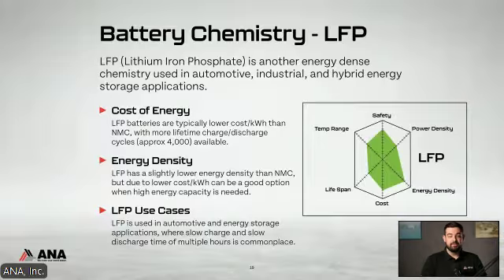Higher operating temperature and typically a 1C continuous rating. You can get all the way up to probably 4 or 5C intermittently for short bursts of time. Lower energy density than NMC, but still not bad. Typical use cases for LFP are energy storage systems as well as EVs, electric vehicles. They're also used as UPS or backup systems for both the medical and the telecom industry.